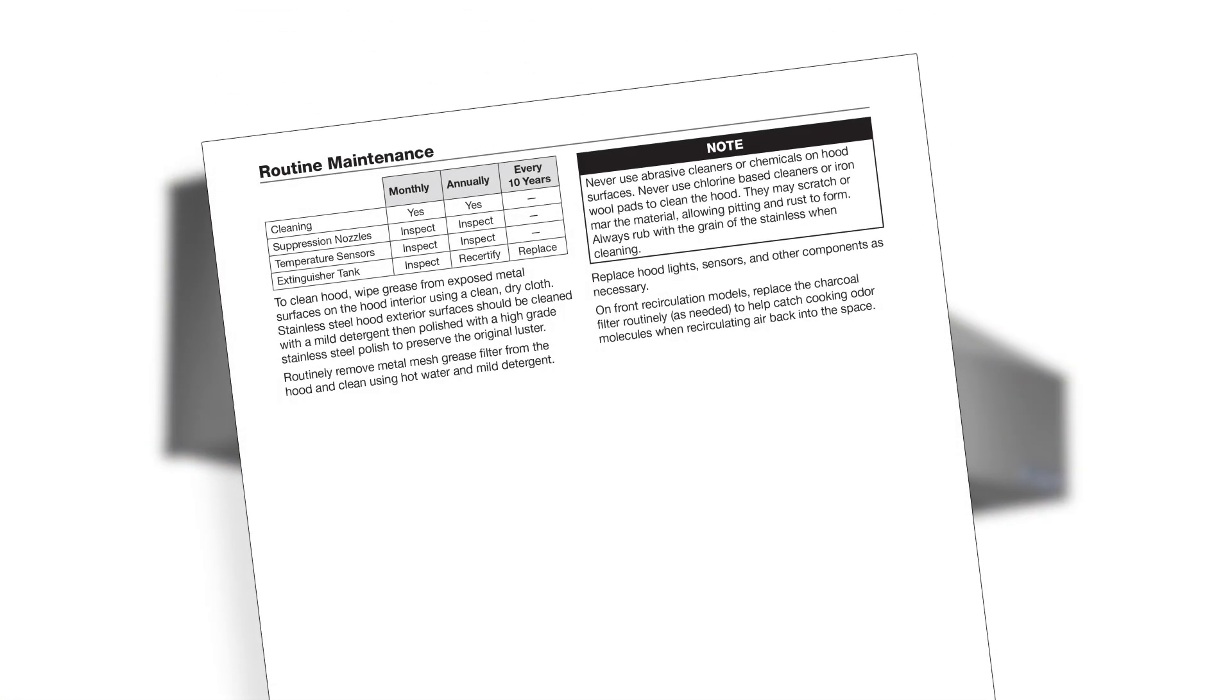For routine maintenance of the suppression system, inspect the tank and verify charge on a monthly basis. Recertify the suppression tank annually. And every 10 years or after a fire, replace the suppression tank.